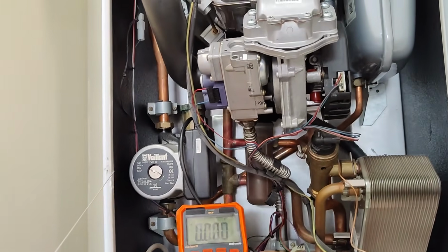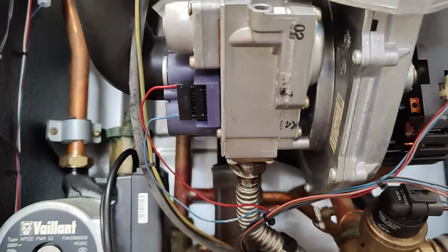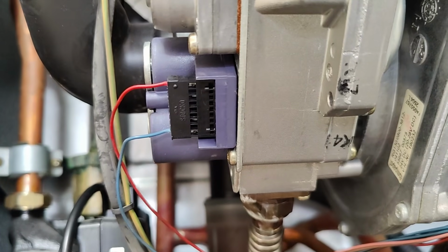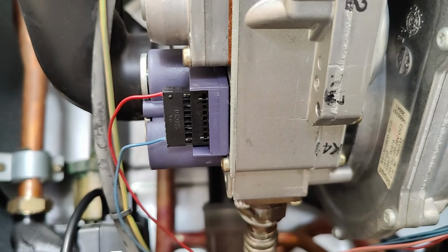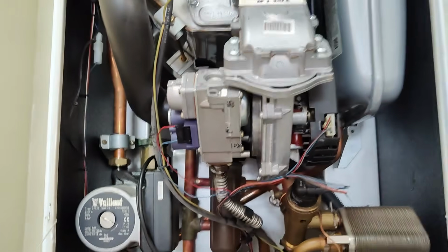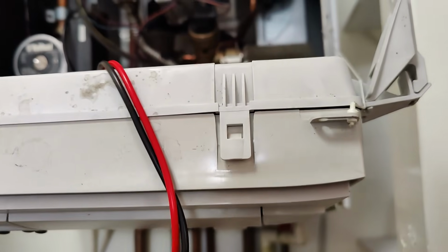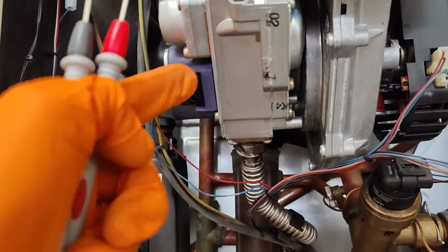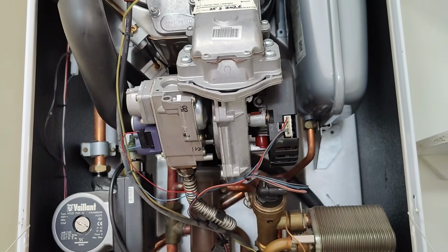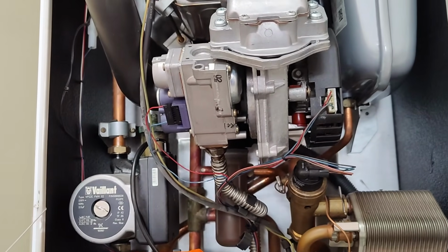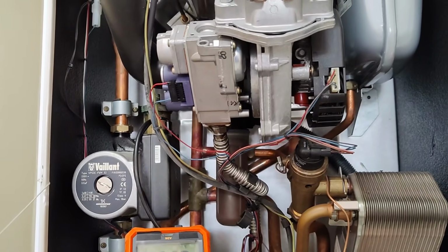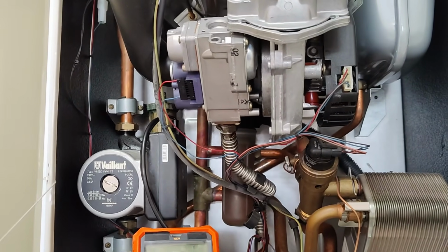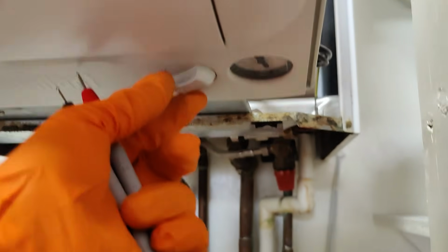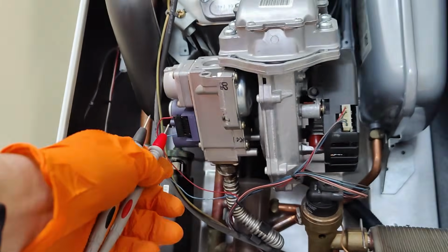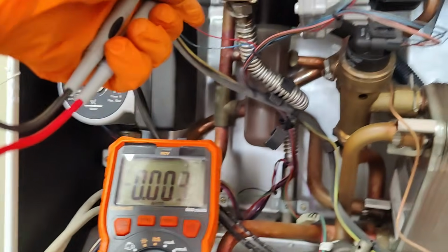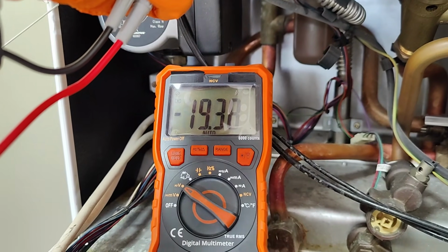Okay, so the next test I want to do is check the voltage coming to the gas valve from the PCB. We're expecting between 20 and 24 volts coming to open the gas valve from the PCB on those two connectors. So I've got the demand for the hot water. I'm just going to turn the boiler on and we will try to get the measurement on the gas valve. All I want to establish is I can hear the gas valve trying to open and close, but whether it's happening due to the voltage dropping from the PCB or it's actually the gas valve, so the voltage is consistent and it's the gas valve spindle that's not pulling out with the solenoid. So let's see. I'm just going to turn the boiler on and try to put these two probes on the valve and see if I've made a good enough connection. You should see voltage, okay?